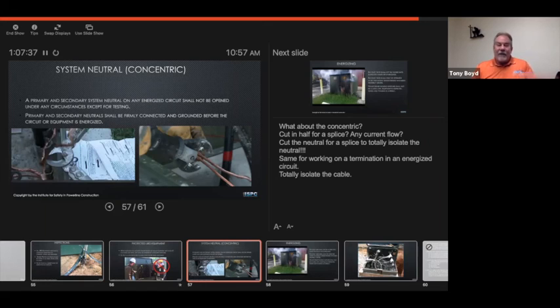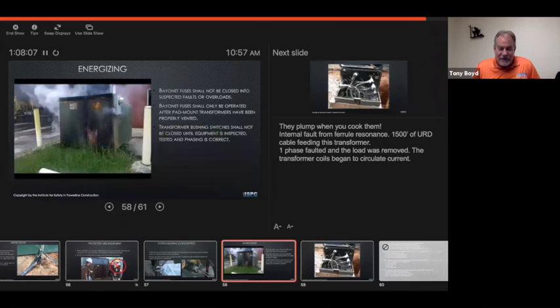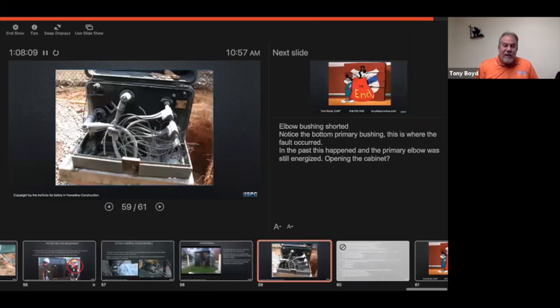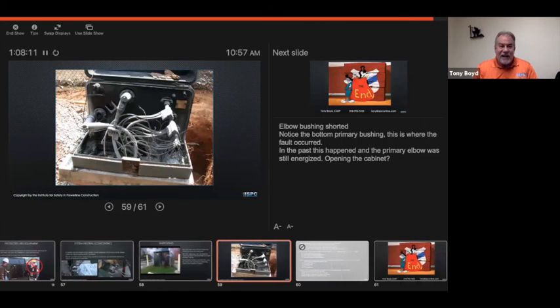So I got down in, we had the splices all together. I got down in and squeezed one concentric neutral and went to squeeze the other. When I grabbed the two, I got a shock. And it wasn't bad. It was enough to make me let go of it. So from then on, concentric neutrals became hazards. I went back and started asking engineers questions as to, okay, what happened? And they explained to me what happened, and explained to me also what the hazard was. So basically, we have a lot of underground hazards out there.